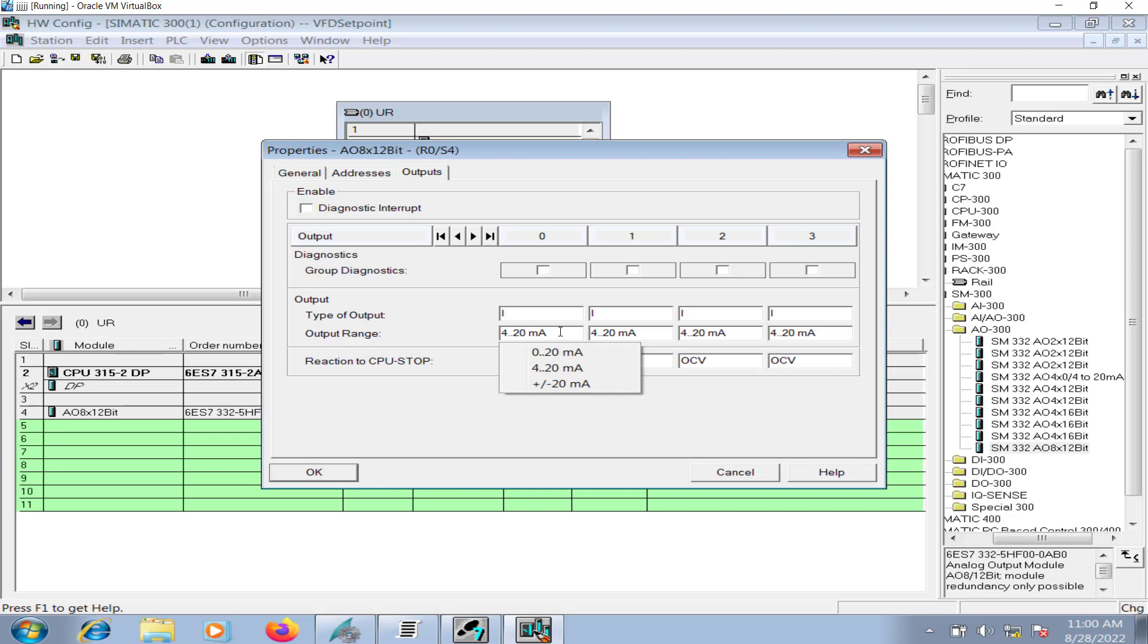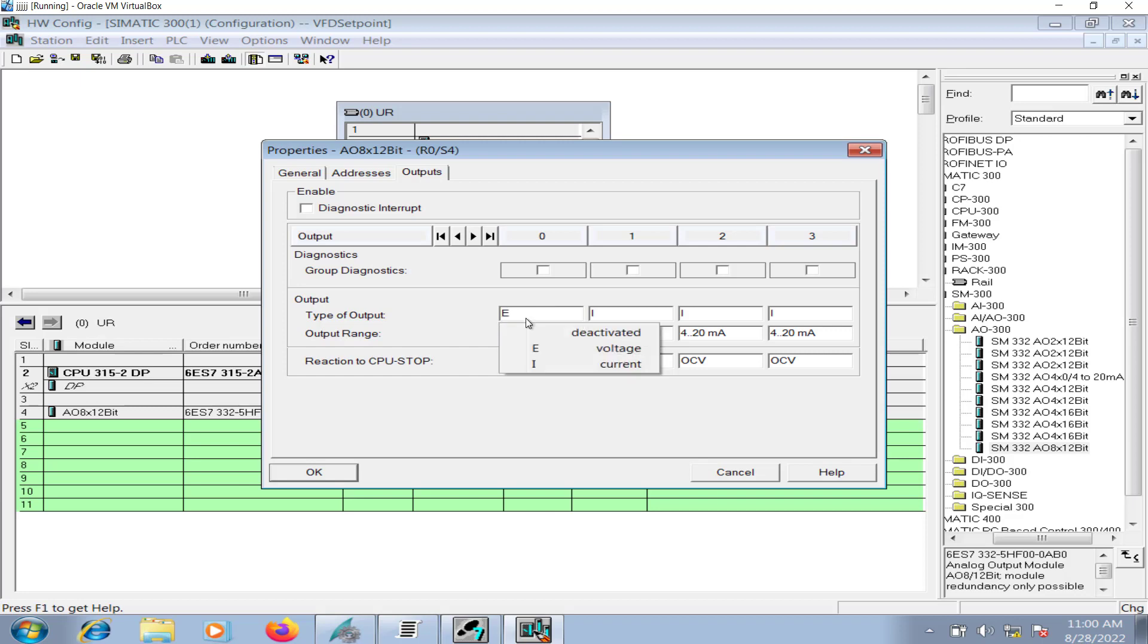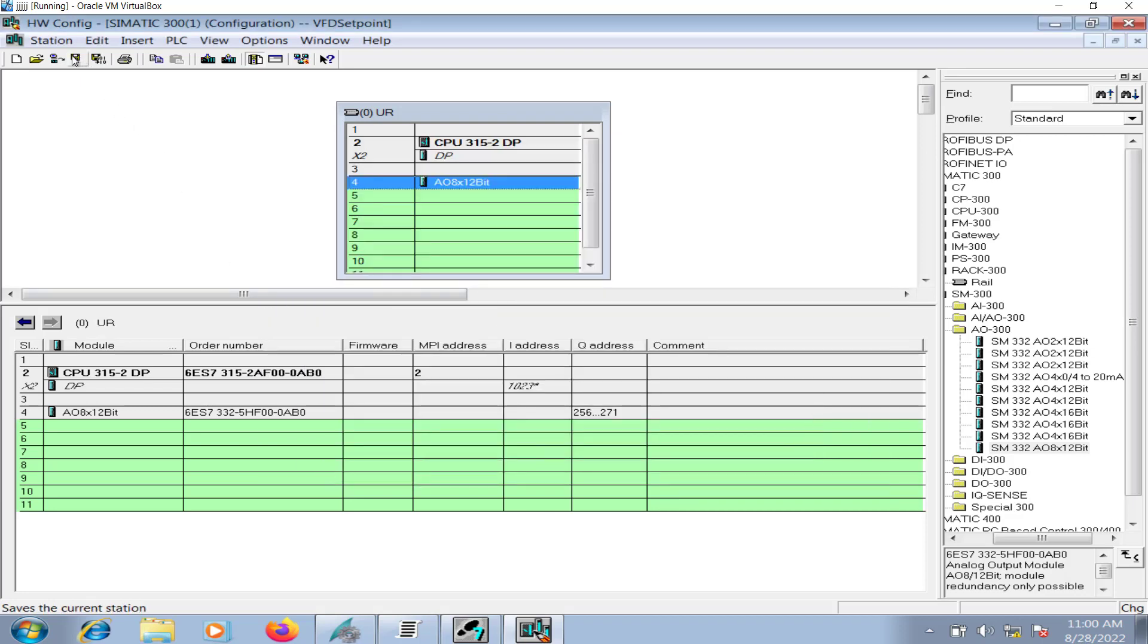I will change the setting to 4 to 20 milliampere. This depends on the VFD configuration. If the analog channel taking the set point value from the PLC has 4 to 20 milliampere configuration, then you must change it to 4 to 20 milliampere. Because these 4 to 20 milliampere DC current will travel from the analog output card of the PLC into the analog input channel of the VFD, so you have to be consistent with the configuration.